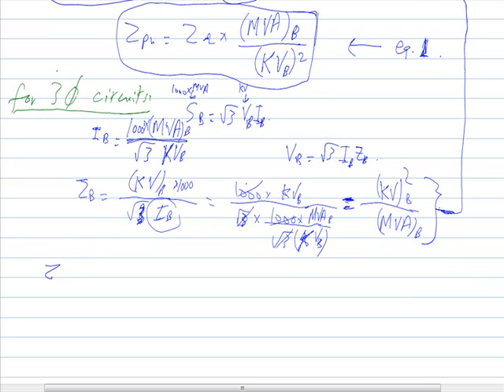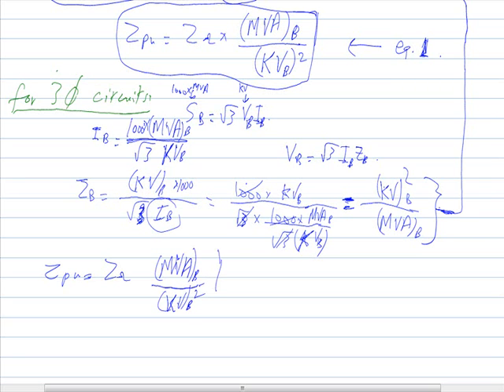The per unit impedance for three-phase circuits is the same formula: the actual impedance multiplied by the MVA base divided by the kilovolt base squared — identical to single-phase circuits. They are identical to each other.